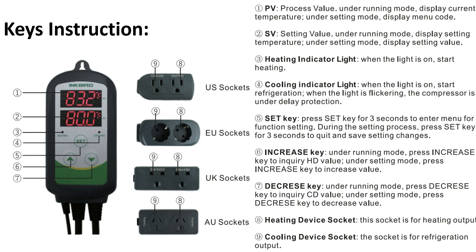This is the SET key. The user has to press the SET key for three seconds to enter the menu for function setting. During the setting process, press the SET key for three seconds to quit and save the setting changes. This is the increase key — under running mode, press the increase key to enquire about the heating differential value; under setting mode, the same key is used for incrementing the value.